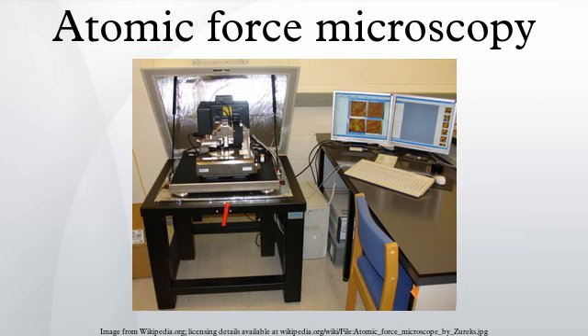AFM cantilever deflection measurement, beam deflection measurement. The most common method for cantilever deflection measurements is the beam deflection method. In this method, laser light from a solid-state diode is reflected off the back of the cantilever and collected by a position-sensitive detector consisting of two closely spaced photodiodes whose output signal is collected by a differential amplifier.